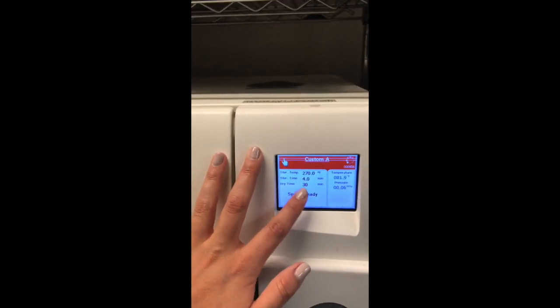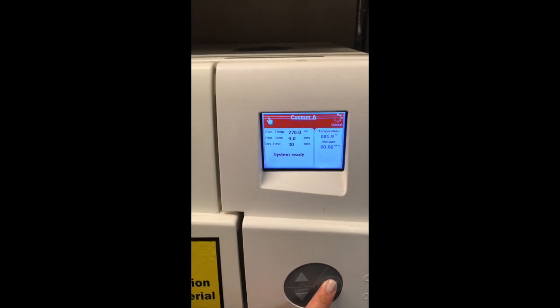So our autoclave is set to 270 degrees Fahrenheit. Sterilization time is going to be 4 minutes. Dry time is going to be 30 minutes. So now I'm going to go ahead and click start, and it will start preheating. And that is how we use our autoclave for sterilization. Okay, so our pressure range for our autoclave is 15 to 27 pounds per square inch. So to sterilize our autoclave, we do it once a month.